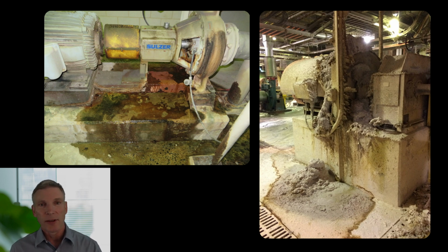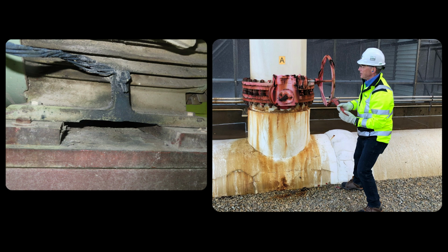Also corrosion in general. You see a big butterfly valve there in front of a cooling tower. We tried to close that up, well, it's not working. I think if we had just put a little bit of coating or paint on that and maintained that over a few years, that valve would last for another 10 years. But now we have to change it out because the gears are already rusted up. We can't open it up.